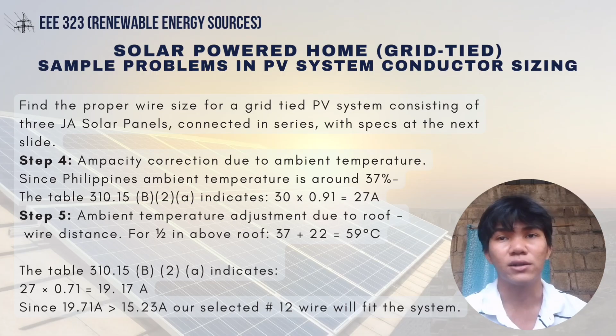For step 6, since there's only 2 wires inside the conduit, yung step 6 ay hindi natin i-count. So, lalampas siya. For step 7, adjustment due to voltage drop. Voltage drop is less than 3%. So, gagamit tayong formula na VD is equal to 2IR. So, yung R is equal to K length over area. So, VD is equal to 2 times 9.3 times 12.9 times 25 over 6,530 ay equal sa 0.92 volts.